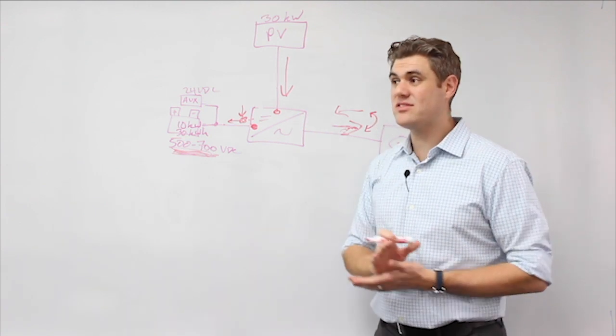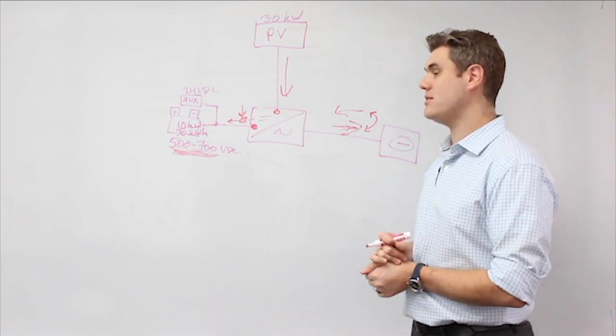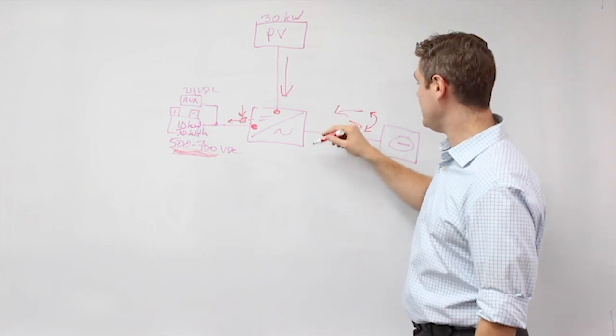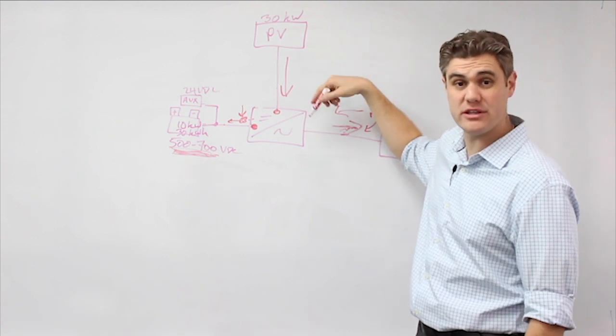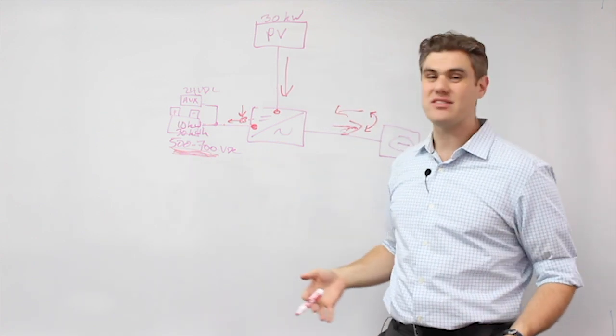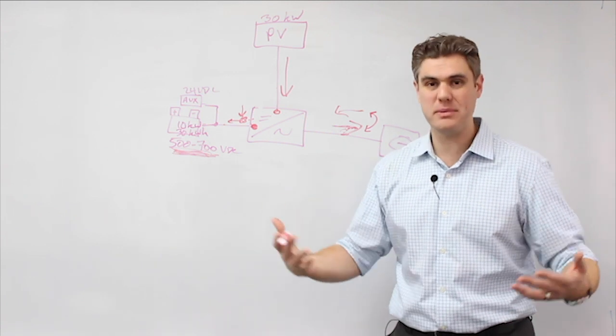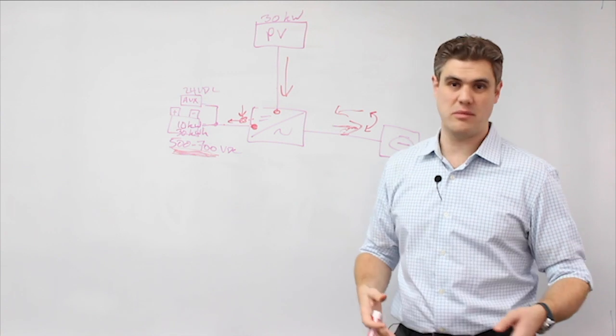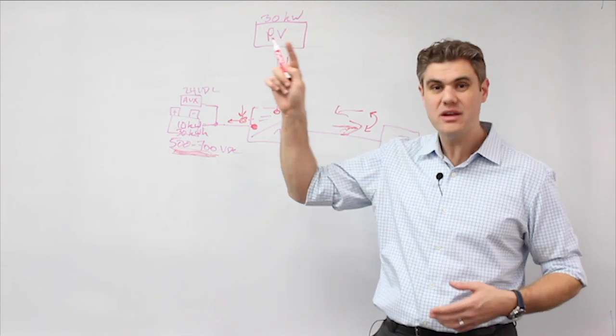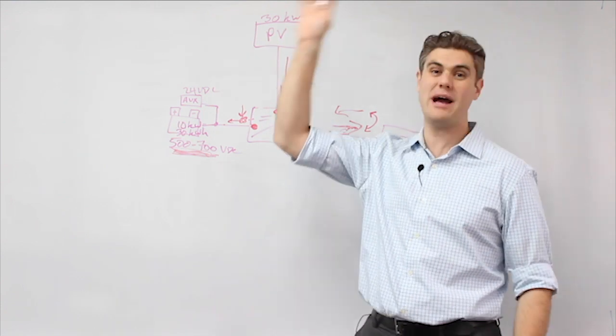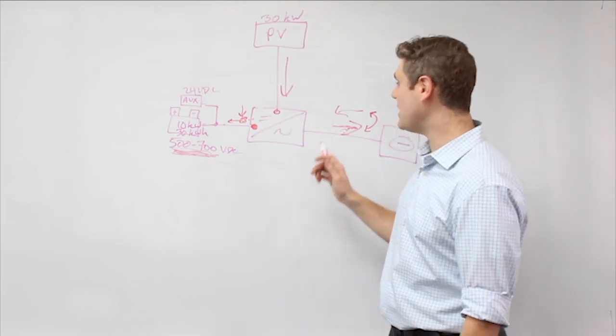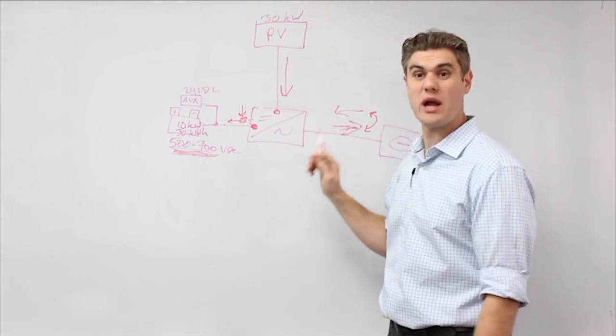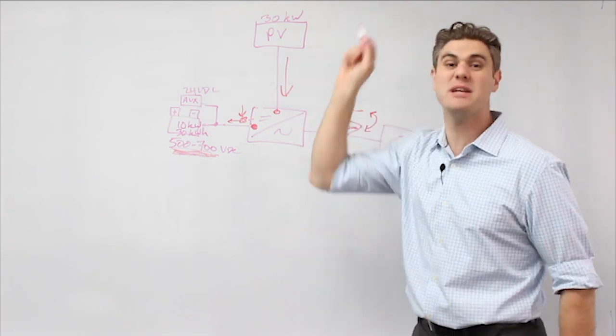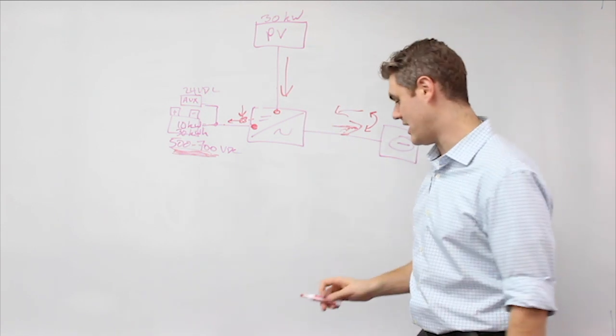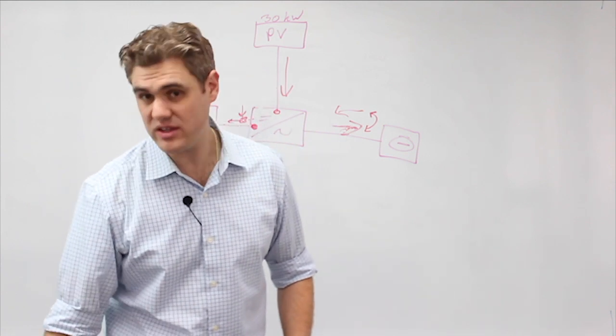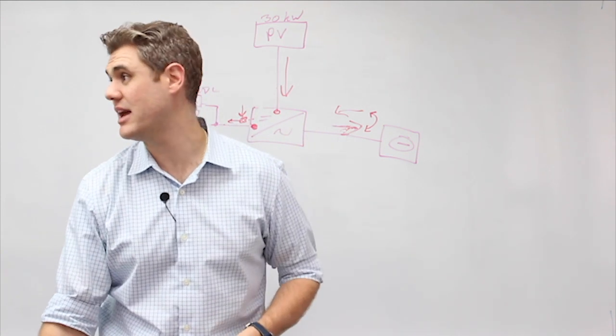And then finally, the last thing that you want to test in all this is what happens when you swing the power up and down on the solar side very rapidly or frequently, because we all know solar is not necessarily always a smooth ramp up and ramp down type of curve, sunrise, sunset. Sometimes there's clouds and weird weather, and you can see the solar turn on and turn off and go from full power to no power in seconds. And so basically it's like a stress test. All these tests I just described all need to be able to work even when the solar is fluctuating up and down very rapidly. So that's the last test that we do, or that UL would do, to see if the solar plus storage system complies with these NEM requirements.